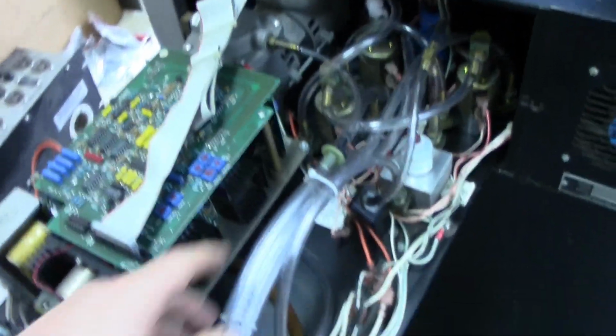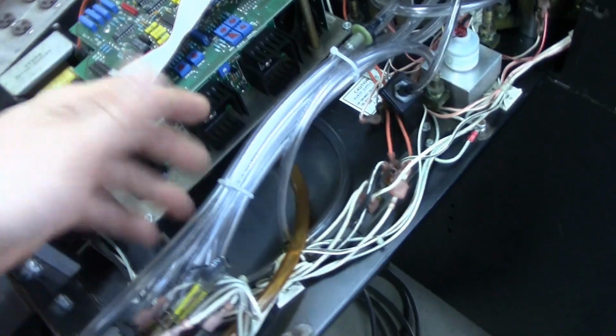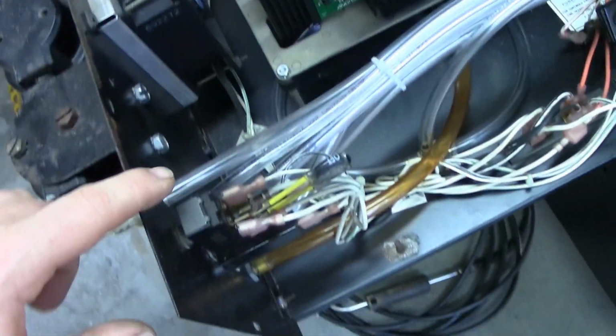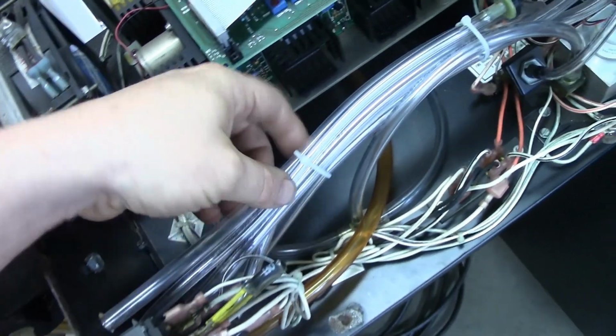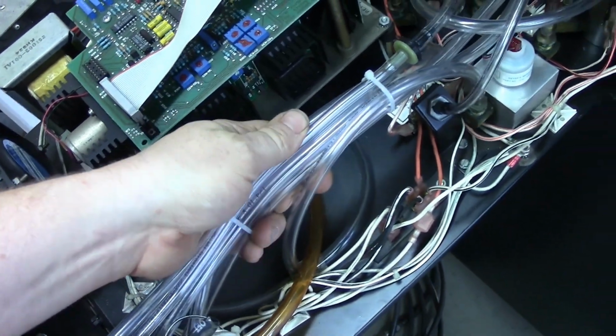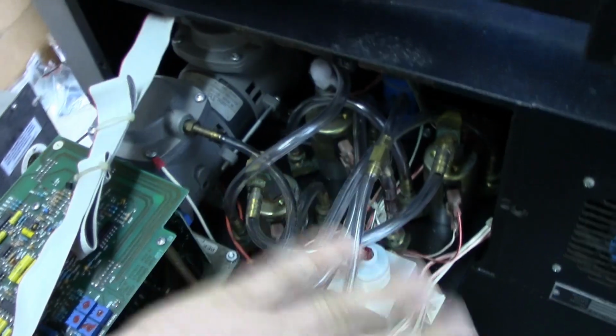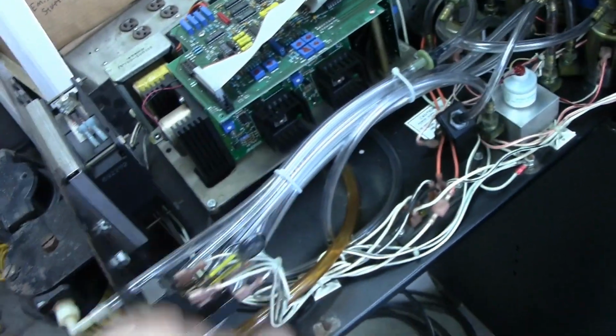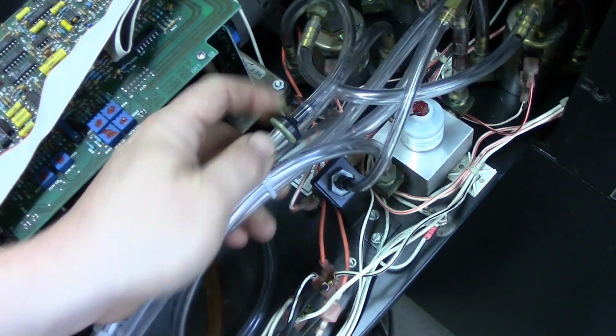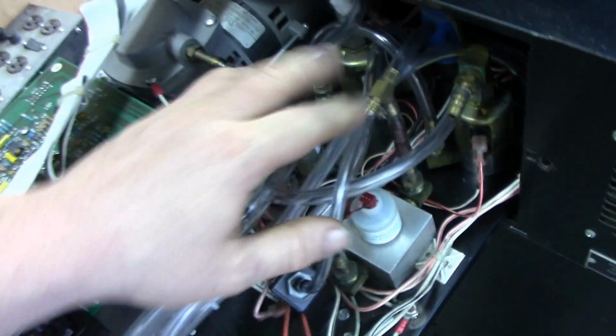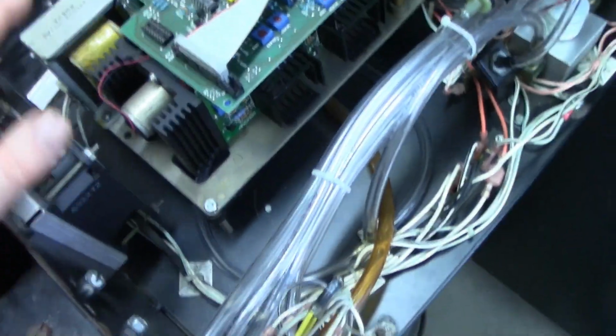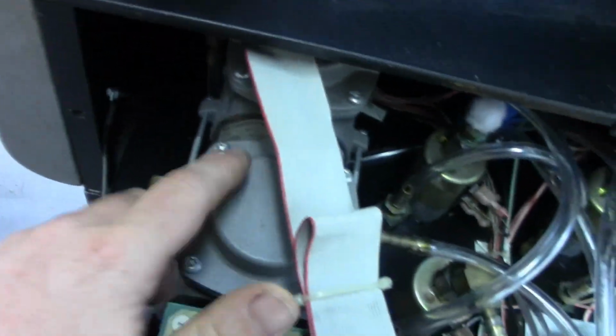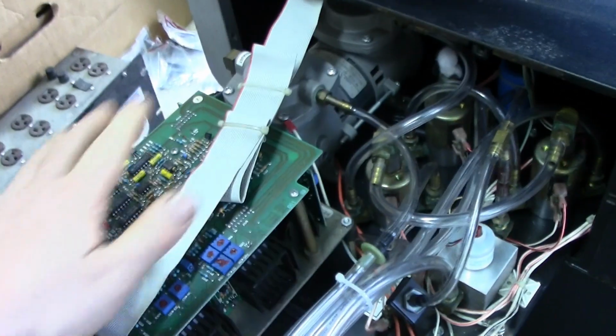Thankfully, for the MEA 1500, on the Internet Archive, someone has archived the service manual. So I have the vacuum routing diagrams for this. So I went in there with food-grade vinyl tubing, because it's low off-gas material, and replumbed this whole thing. So this actually works. This is interesting because it has a check valve, there's a restrictor there, all sorts of things that will just kind of break and fall off and go missing. It's kind of annoying. But the gases in here are analyzed, they come in, it uses this Thomas vacuum pump that's hiding back here, and it just pulls into the system.